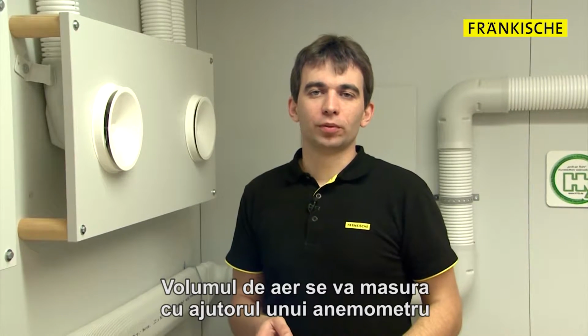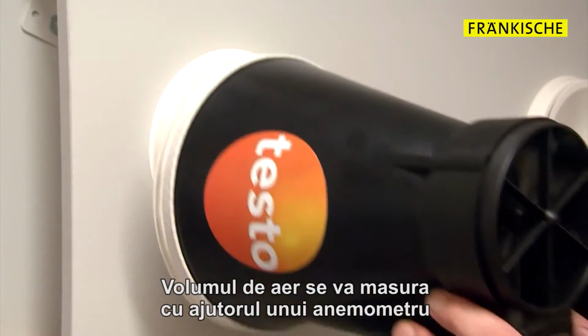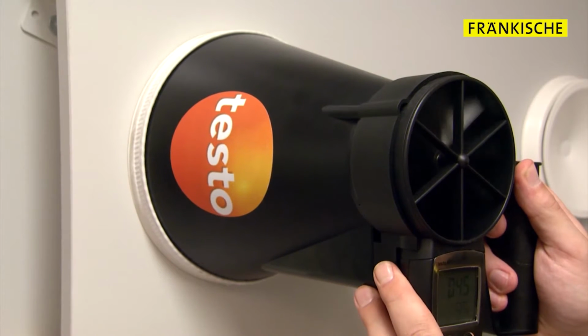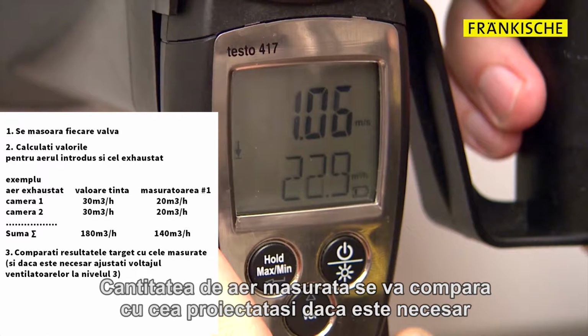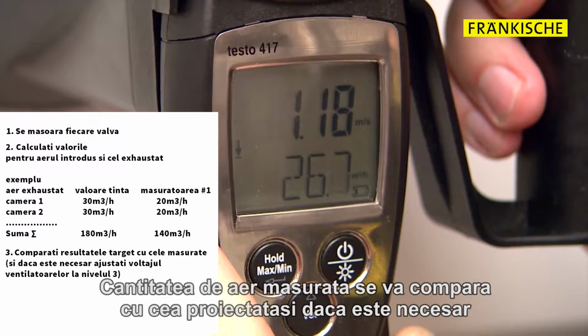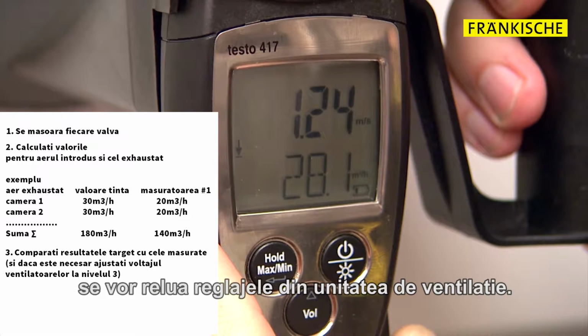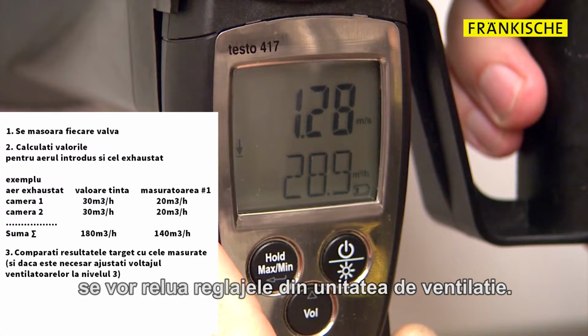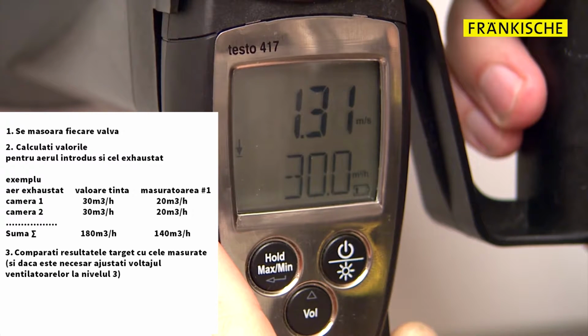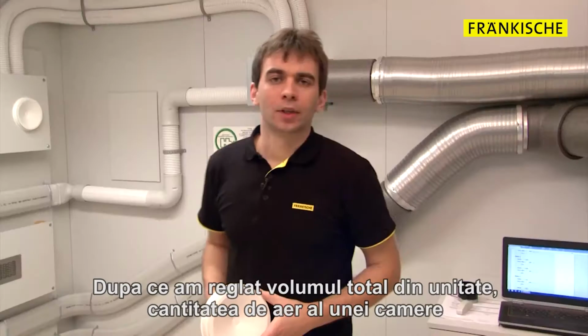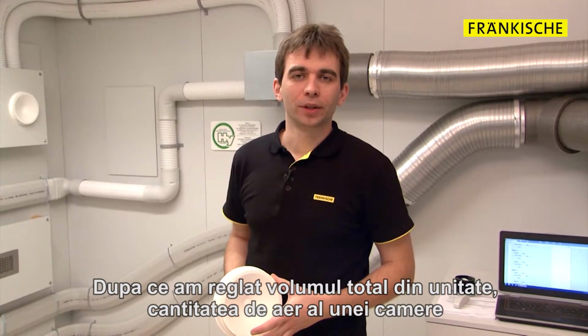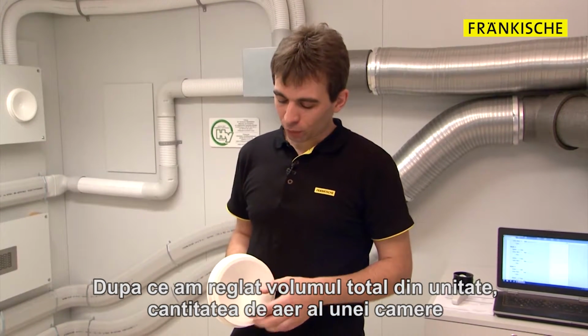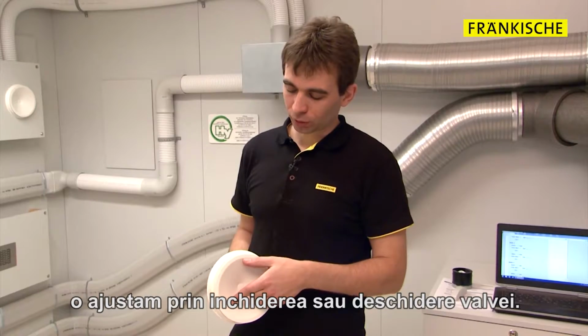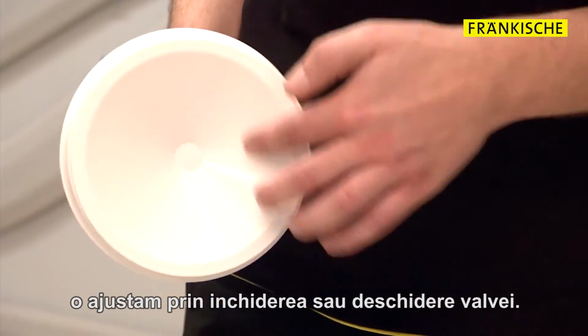The air volume flow rates are measured using an impeller anemometer. The measured total air volume flow rate is compared to the planning value, and if necessary, the values must be adjusted once again at the ventilation unit. Having adjusted the total air volume flow rates, the room air volume is adjusted by opening or closing the valves.